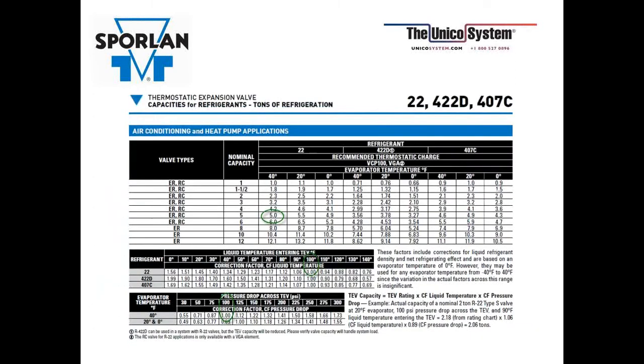And these might be hard to see, but hopefully you can follow along. If not, they're actually straight out of our bulletin 1010, which is our expansion bulletin. And this is from the capacity charts. Here's an example of the nominal capacity of an R22 valve for the ER series TEV. Notice the nominal capacity is 5 tons. It's circled up there. Using the previous chart, we know that for a 40-degree evaporator, 100-degree liquid, and 100-pound pressure drop through the port, the correction factors are both 1, so the actual capacity is still 5 tons.